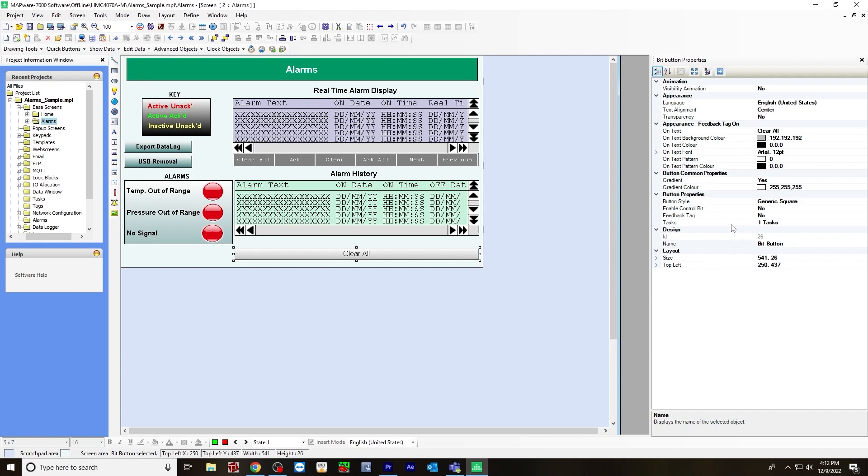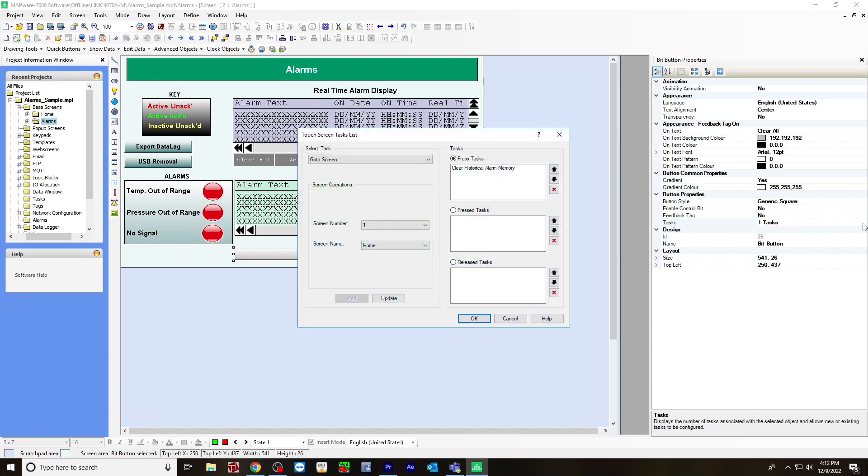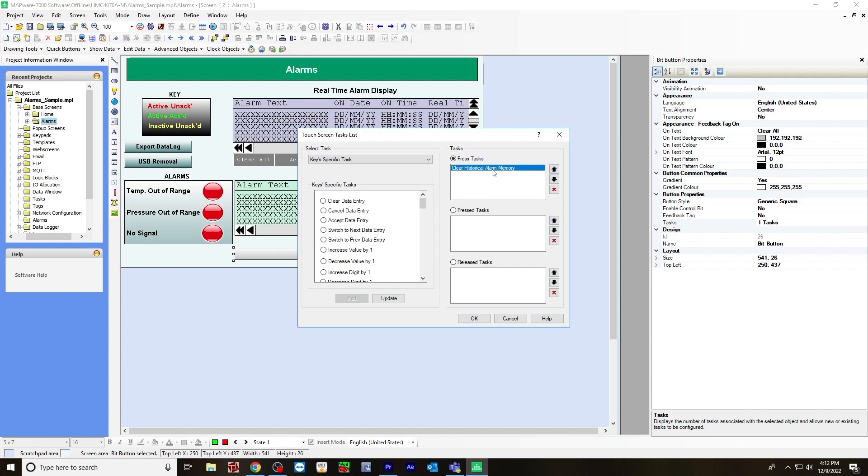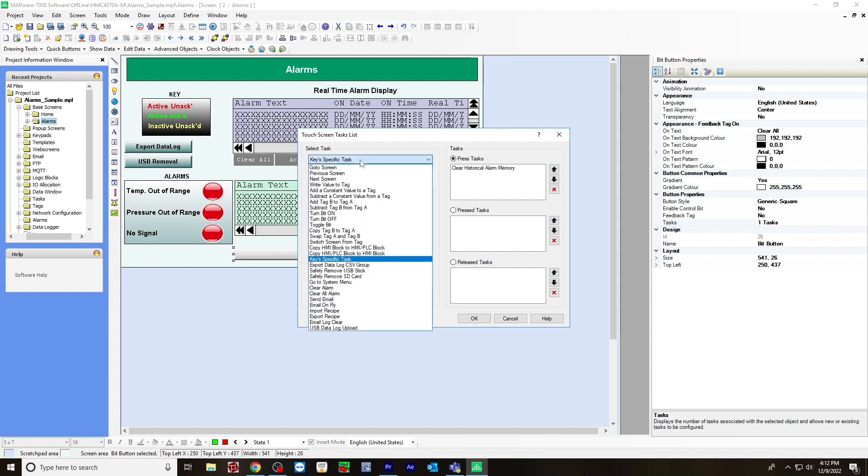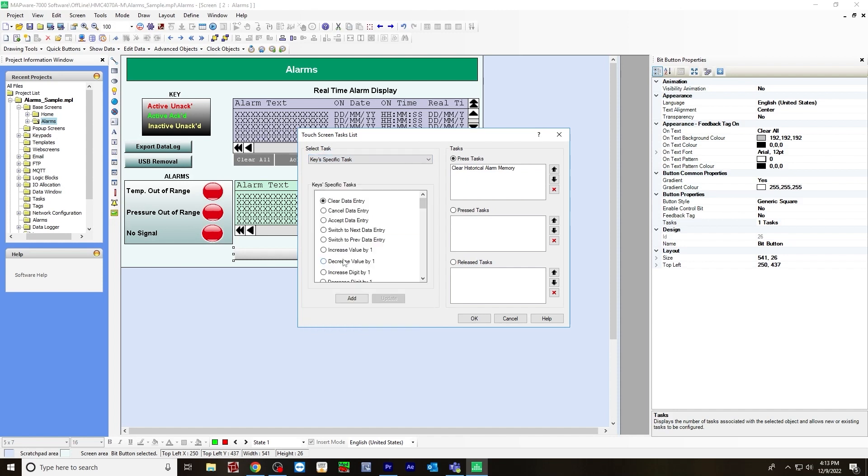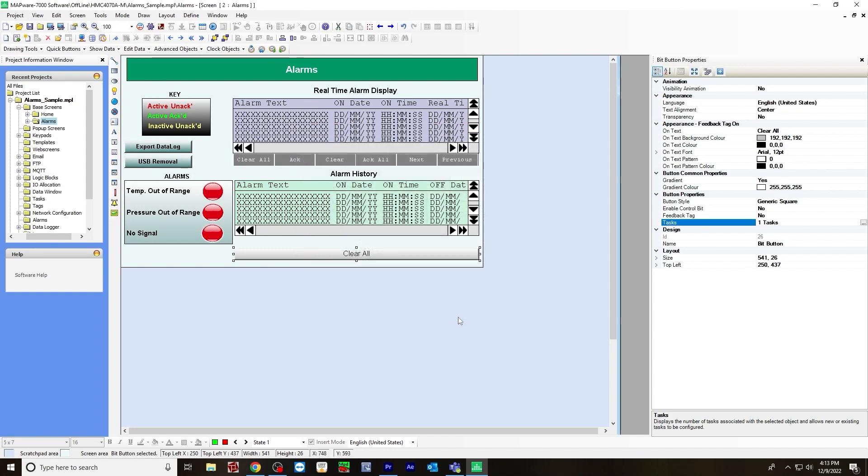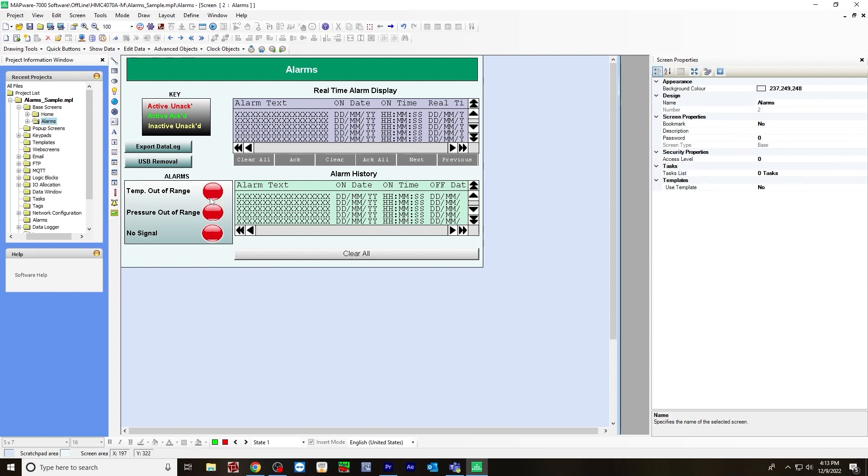For this, I chose the on text to say clear all. For the task, I chose for a press task, clear historical alarm memory. You do that by selecting a task, it'd be a keys specific task. I scroll down and chose clear historical alarm, and I added it over here. Now when I click this button when I'm online, it'll clear all the alarms in the alarm history.